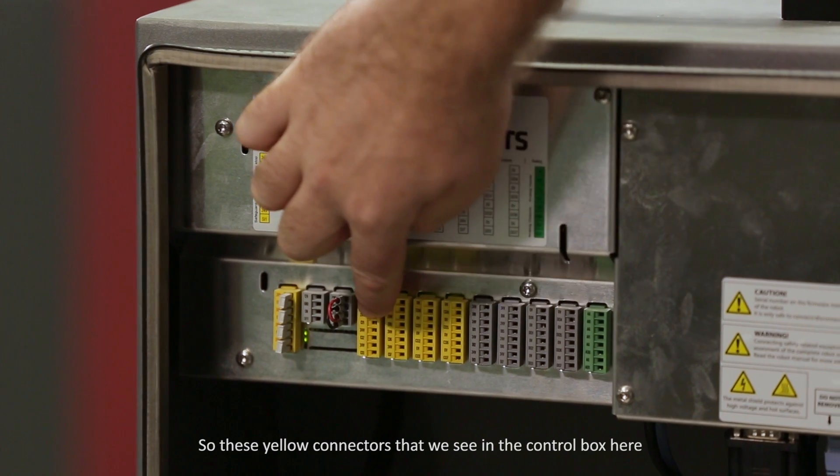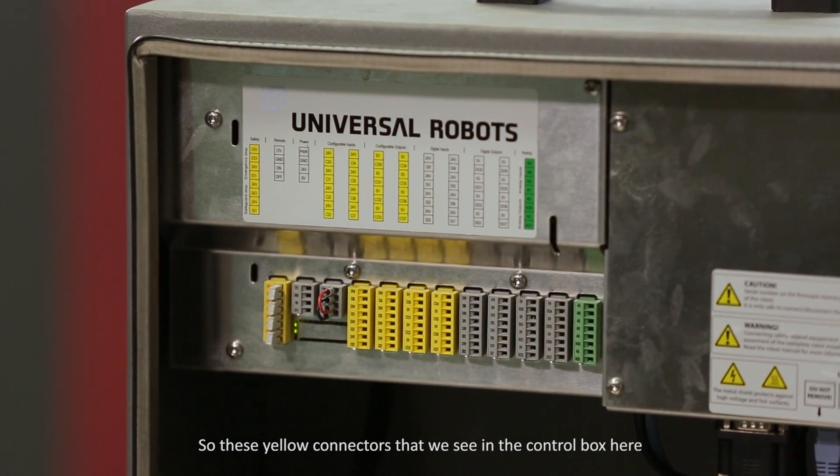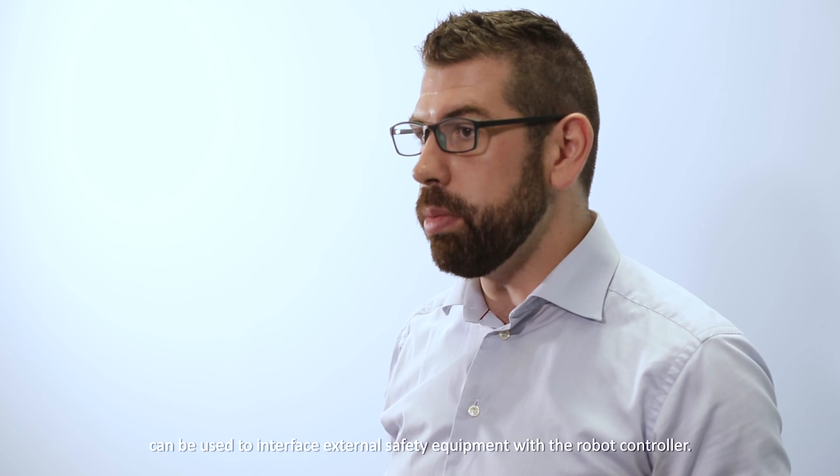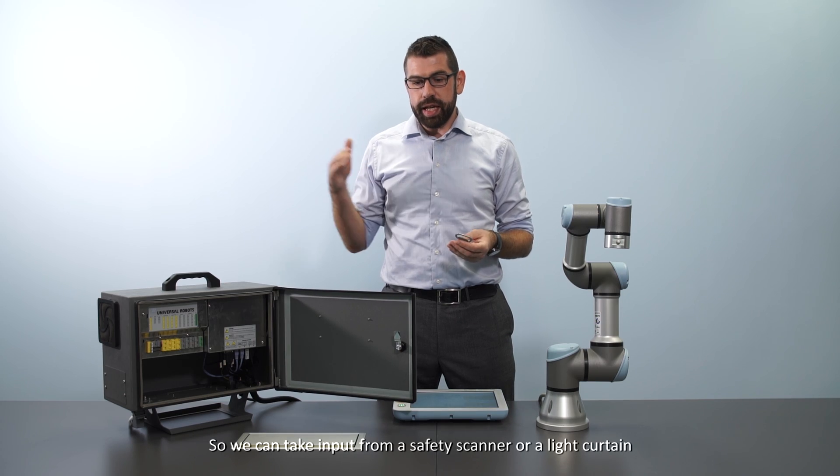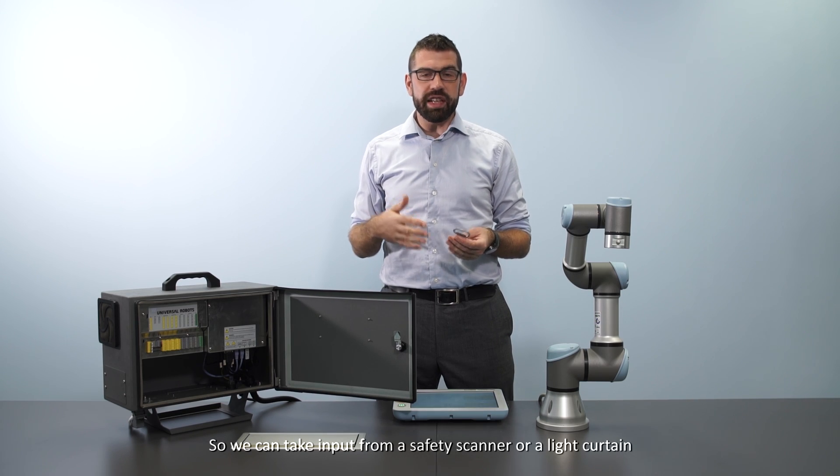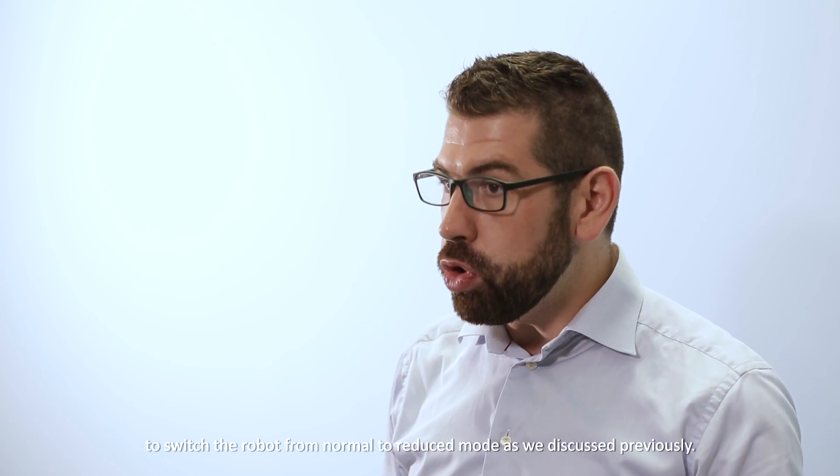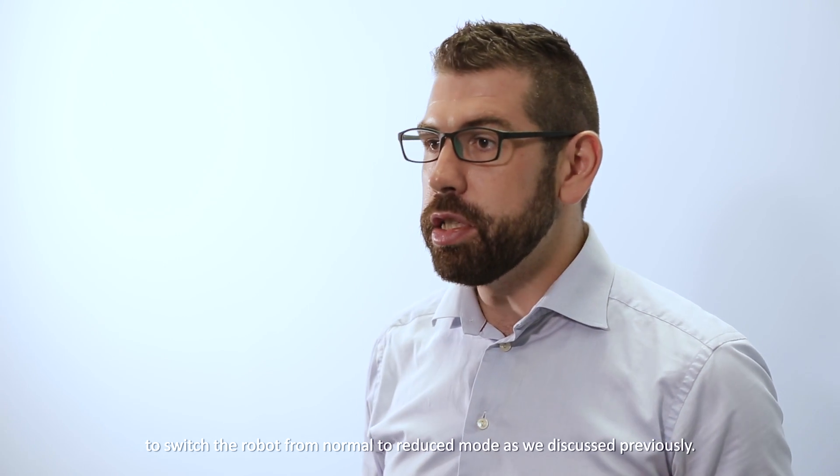These yellow connectors that we see in the control box here can be used to interface external safety equipment with the robot controller. We can take input from a safety scanner or a light curtain to switch the robot from normal to reduced mode as we discussed previously.